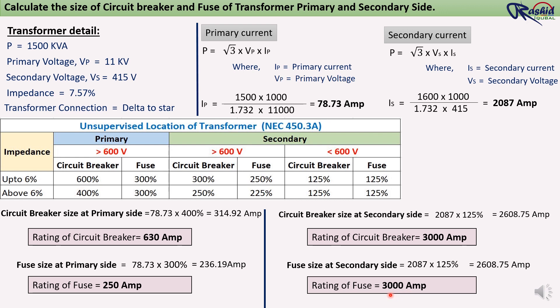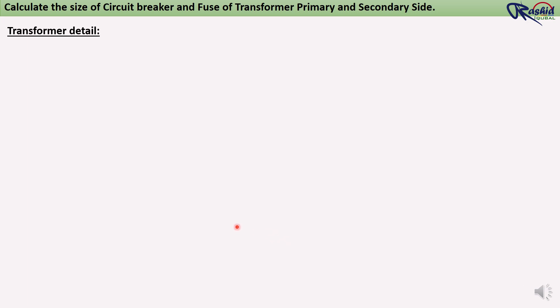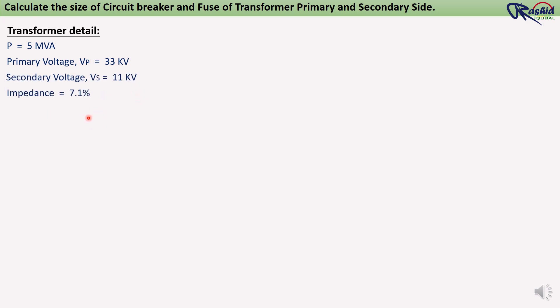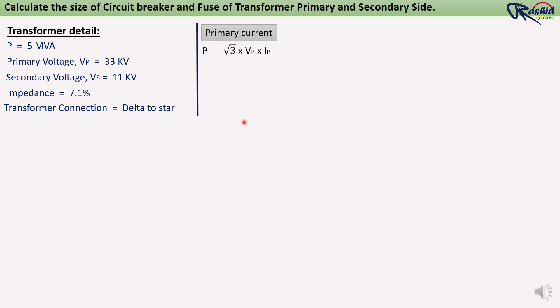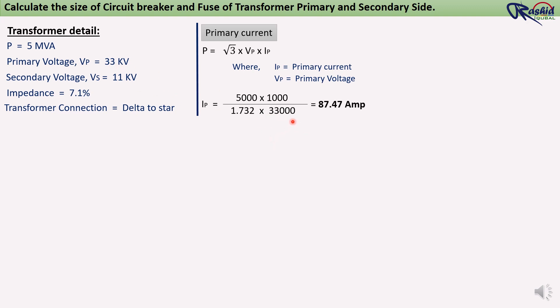Let's take one more example for a power transformer. Here we are using a 5 MVA rating transformer. Primary voltage is 33 kV and secondary voltage is 11 kV. Impedance is 7.1%, and transformer connection type is delta-star. For primary current: Ip = (5000 × 1000) ÷ (1.732 × 33,000) = 87.47 ampere.